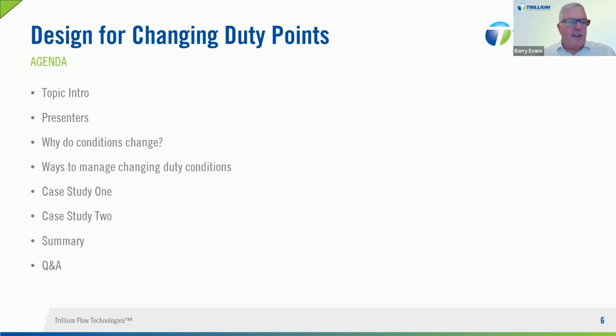And the result of that is often that the pump optimum duty selection is based on a requirement which has got a lot of contingency built into it. And this can then be different both at the initiation phase and through time. And that's before we take into account any system lifetime changes, upgrades, debottlenecking, expansions, variations in demand, and lifetime projections.